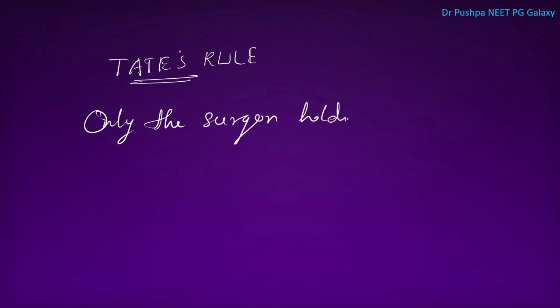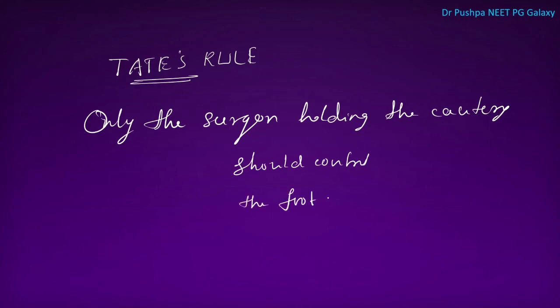In monopolar cautery, there is a single end acting as the active electrode, and the ground plate acts as the return electrode — the patient is part of the circuit. In bipolar cautery, there are two tips: one as the active electrode and another as the return electrode, forming a circuit between those two tips. There is something called Tate's rule: only the surgeon holding the cautery should control the foot pedal.